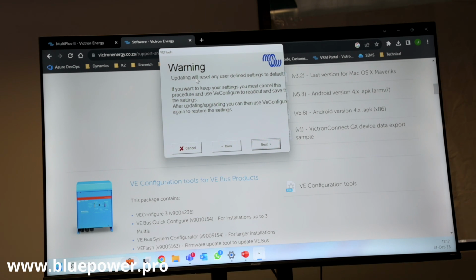Now it's giving us a warning stating that updating will reset any user-defined settings to default. So if you've got a running system that you want to update, and you want to retain those settings, you'll have to close the firmware update, open VE Config, save the settings file, and then re-open VE Flash and continue. But if you've got the manual at hand and you know the settings are standard, not something special, you can just update the firmware and reconfigure the system yourself. But do note that if you update the firmware, the system gets reset to defaults, all settings.